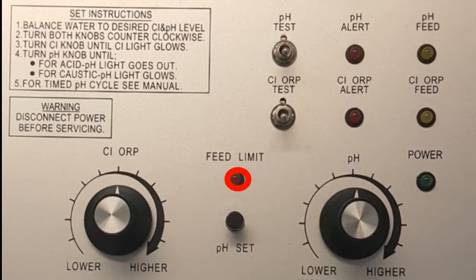This is an optional feature of your controller. When this LED is lit, it's informing you that one of the feed systems ran for 4 hours continuously. It is normally an indicator of a problem with the feed system or an electrode failure. The controller will cease to operate until it's manually restarted, which is accomplished by unplugging the controller from the power source and plugging it back in.